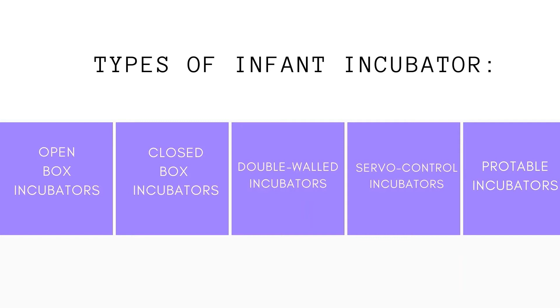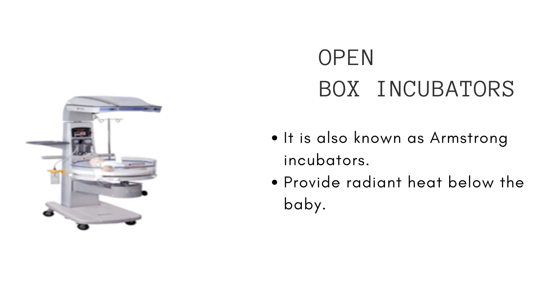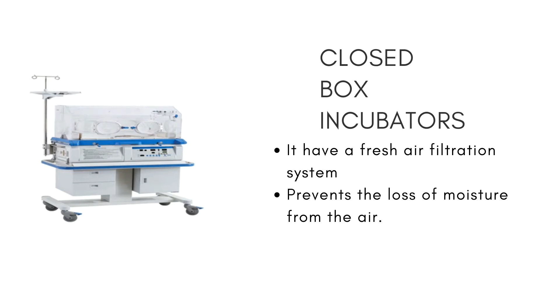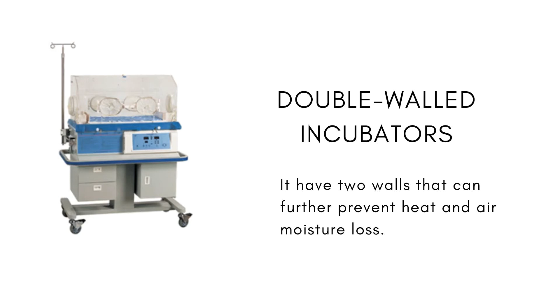First one is open box incubators. The open box incubator, also known as the Armstrong incubator, provides radiant heat below the baby but is otherwise open to air, allowing for easy access. Next is closed box incubators. They have a fresh air filtration system that minimizes the risk of infection and prevents the loss of moisture from the air. Next is double walled incubators. They have two walls that can prevent heat and air moisture loss.